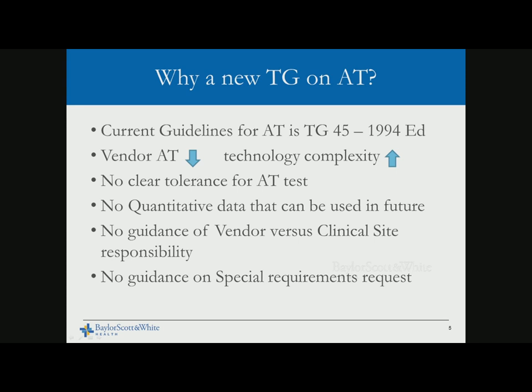Although there is no clear tolerance for acceptance testing — we have recommendations from TG 142, TG 106, and others — when vendors use their own proprietary tools and phantoms and calculate tolerances on their own criteria, it is very difficult to compare what is acceptable. Another issue is quantitative data for future use: if a major part changes three years later, is there any way to quantitatively compare how the LINAC was during acceptance testing and now after that part change?